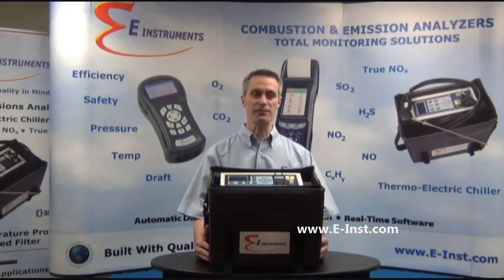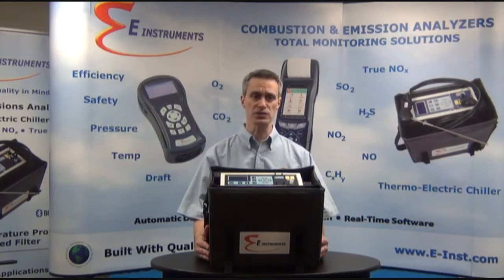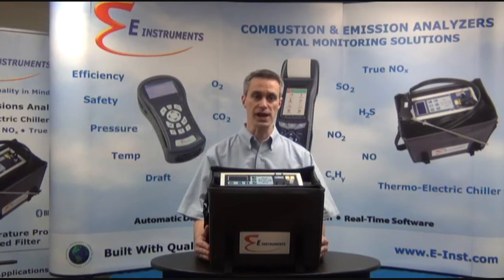When shutting down the E8500 Plus after testing is completed, it is recommended to purge the analyzer with clean air for a few minutes with the hoses connected and then an additional 10 minutes or more with the hoses disconnected before completely turning off the analyzer, as this will purge any toxic gases and help better protect the sensors and lengthen their lives. Our factory recommendation for recalibration of the analyzer is at least once each year.